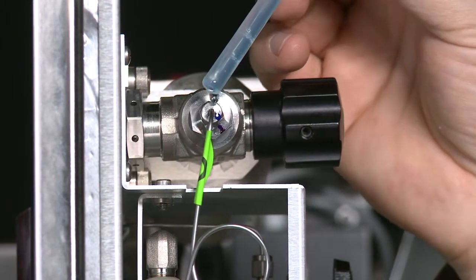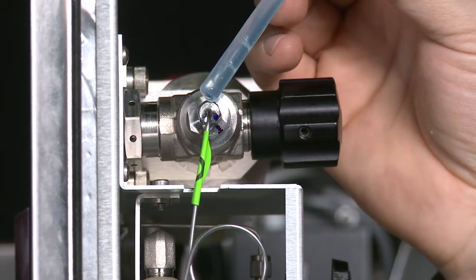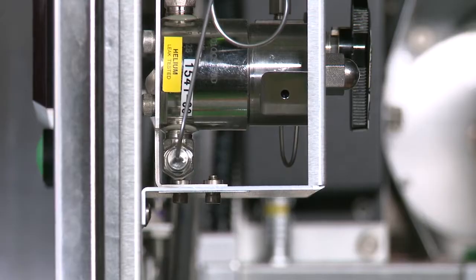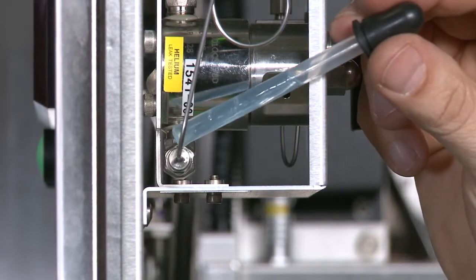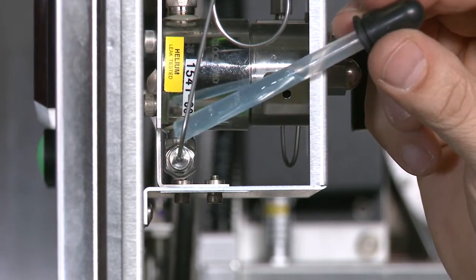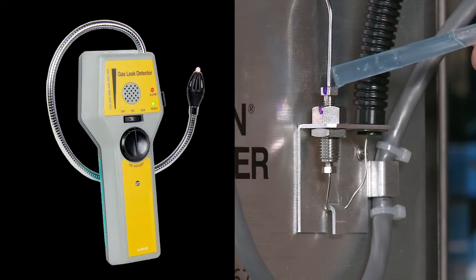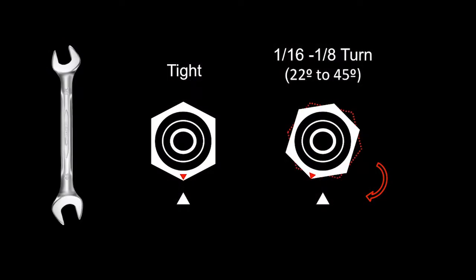If a leak-checking fluid such as Snoop or Big Blue is available, it is recommended to check the accessible fittings, particularly those that have been connected in the field. A portable helium leak detector may alternatively be used to sniff for leaks around the fittings on a wind-still day. If a leak is detected, tighten the leaking fitting by 1/16 to 1/8 of a turn. If the leak persists, contact Morgan Schaffer.